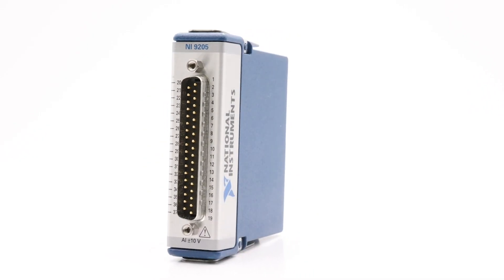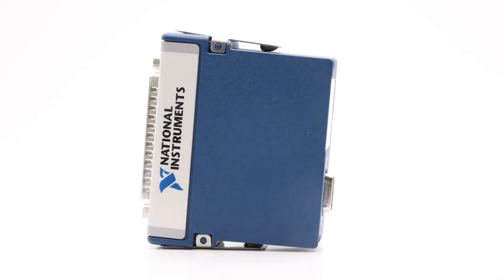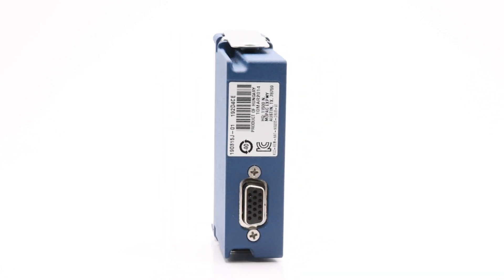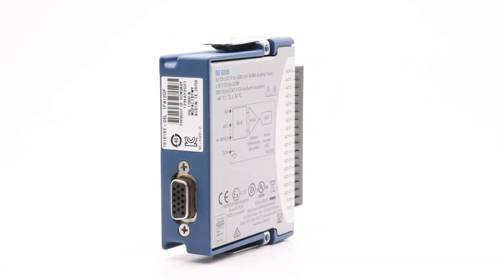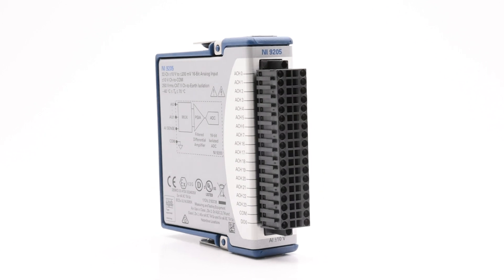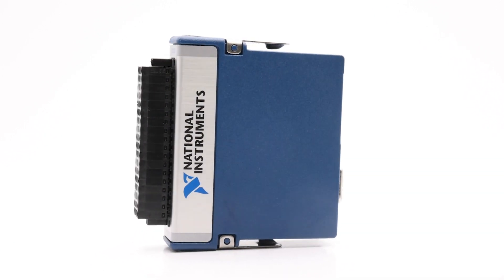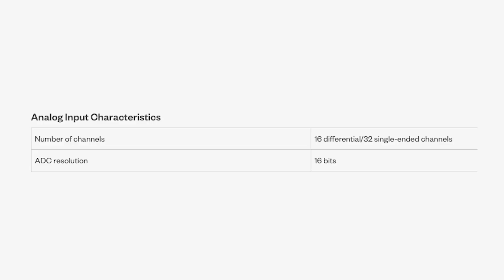The NI9205 is an advanced C-Series voltage input module manufactured by National Instruments. This module can be used with NI CompactRIO and CompactDAQ chassis and is structured with 16 differential analog input channels or 32 single-ended analog input channels with an analog input resolution of 16 bits.